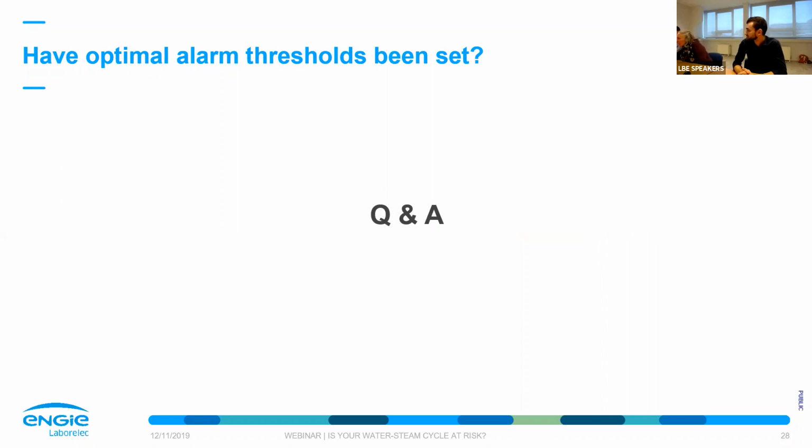Are there any specific guidelines for solar plants? We have a startup and shutdown every day, and sometimes during the same day we can have 2 startups, which disturb the chemical quality of the water or steam cycle. It is very difficult to reach the normal values established by the ST supplier or EPRI. Yes, so this is also the problem of a lot of CCGT plants that are running in a high flex mode.